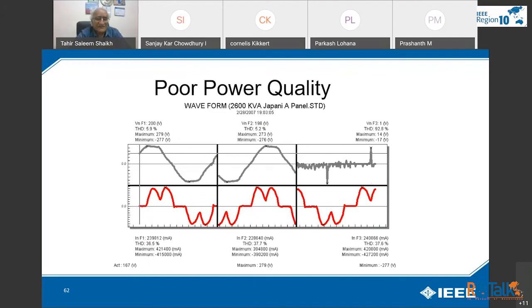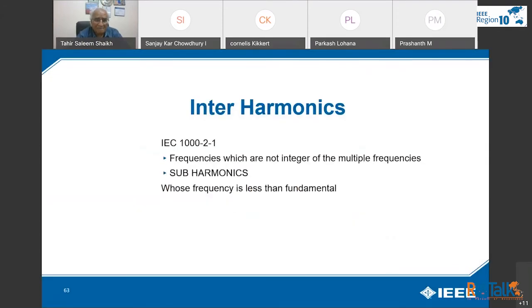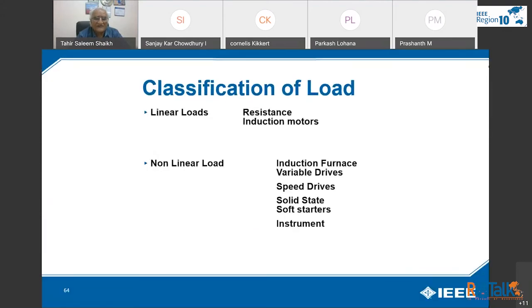This is very high. Normally, as per global standards, it should not be more than 10%. If the environment is very critical for power electronics equipment, it should not be more than 5%. IEC 1000-2-1. Frequencies which are not integer multiples of the fundamental are called subharmonics if their frequency is less than the fundamental. We will not discuss interharmonics in this presentation, but they also create problems.